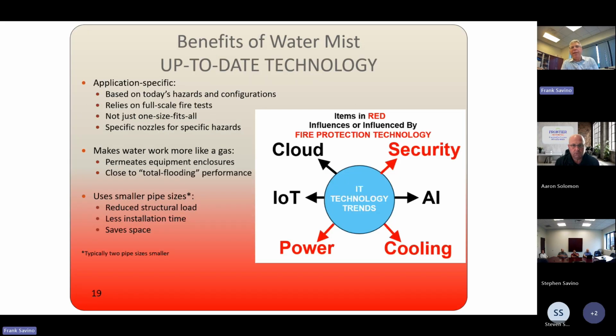Today there's a lot happening in the data center space. There's cybersecurity. Everything's gone to the cloud. You've got the Internet of Things. Power requirements are way up. Cooling requirements, as a consequence, are way up. And this is all being driven by AI, which is going to be the next new industrial revolution in our country, everybody's saying. So the thing to know about water mist is that it is application specific. What that means is it's based on specific hazards and configurations. In order to get approval for a particular hazard, it's required that the application is full scale fire tested. And unlike sprinklers, it's not one size fits all. There are specific nozzles for specific hazards, and we're going to get into that shortly.